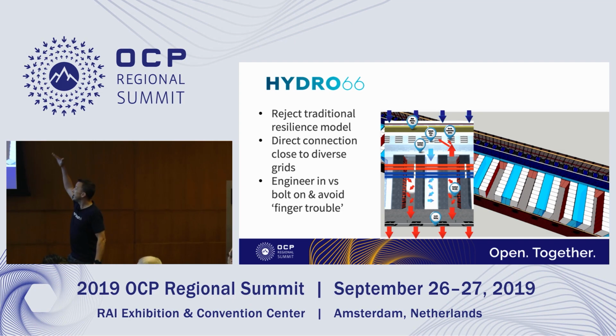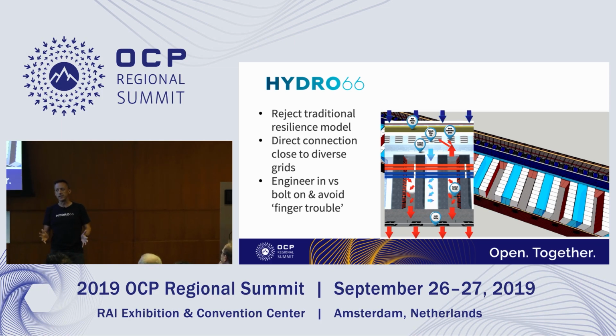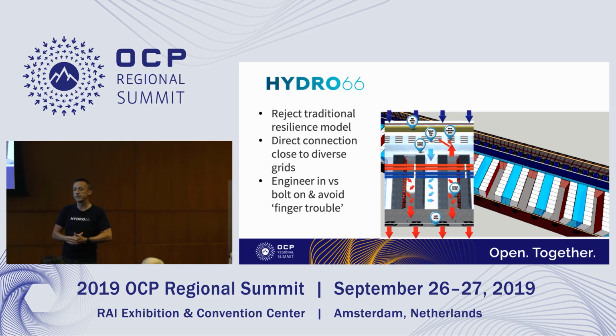So we literally just take in the air from the top there, spin it through some fans, into the cold aisles and out through the servers. Now in winter, minus 30 degrees, not so great. As John mentioned yesterday, if you hit a wet pad doing humidification with minus 30 degree air, it's going to freeze. So instead what we do is recirculate some of the air, reusing that heat to bring the minus 30 degree air back up to a set point of 18.2.